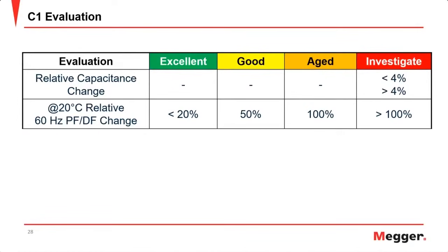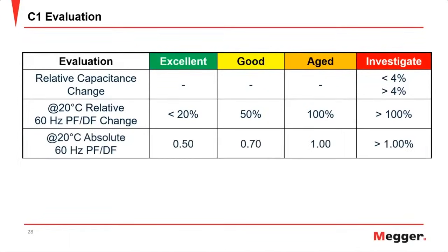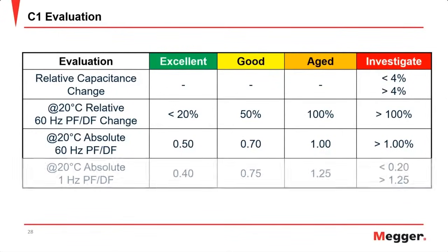Now, let's say you don't have the nameplate values. You can look at the absolute power factor values at 20 degrees C. So again, if you don't have that nameplate value, then standard practice would be to evaluate the absolute values. We're looking at 0.5 for excellent, 0.7 for good, 1.0 for aged, and anything above 1% would be cause for additional investigation. Finally, here at Megger, we do have evaluation of 1 hertz in addition to the 60 hertz. You'll see that it has the same sort of increase from excellent to good and aged. For investigate, we expect values below 0.2 or above 1.25 to be reason to perform some additional tests on that bushing.